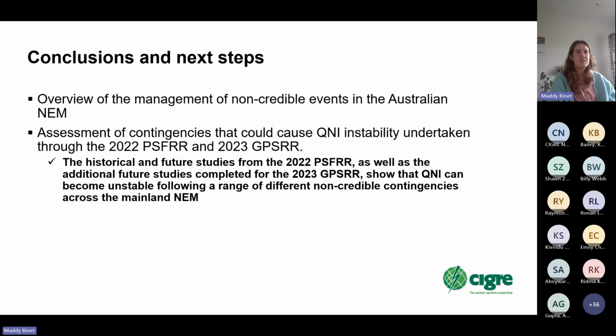In the last risk review, we did try to highlight possible unexpected cascading failures, like additional loss of generation. We try to build a lot of fat into what we recommend. For instance, for the UFLS screening studies looking at UFLS adequacy, we trip off lots of different combinations of stations to try and work out what the worst case would be, or what the requirement is in terms of how much we should protect for.